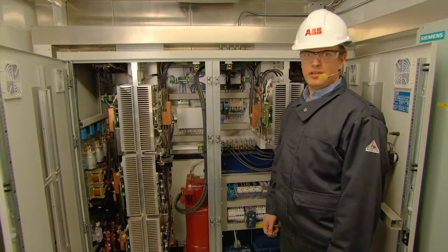The low frequency plant consists of one major unit, and that is a frequency converter standing behind me. And then there is a control system controlling the frequency converter. It's also controlling the other equipment connected to the plant, such as the vacuum valve, the pressure sensors, the thermocouplers, and the vacuum pumps. We will now show you a demonstration about the plant, how it is working, how it is set up, the main components and equipment around the plant, how to connect them to the plant, and how to operate the plant.